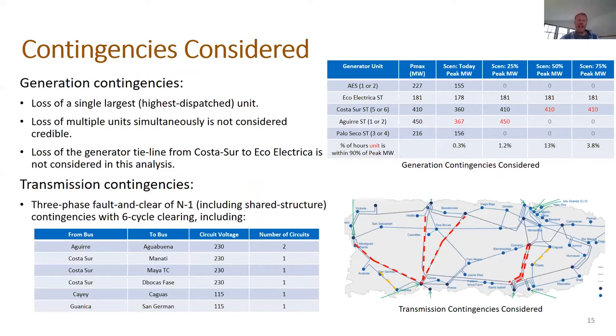We looked at two broad categories of disturbances or contingencies, the first being generation contingencies and the second being transmission contingencies. So on the top, with generation contingencies, we consider the loss of the single largest or highest dispatch unit at a given grid condition based on the results from the operations analysis that Derek was describing. We did not consider multiple units simultaneously. And one note, that Ecoelectrica is a bit of a special case in that the plant is connected to the rest of the grid via one transmission line. We only considered Ecoelectrica in a loss of one of the units, not a loss of the entire plant.